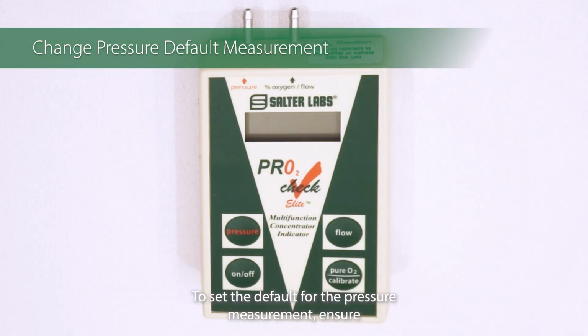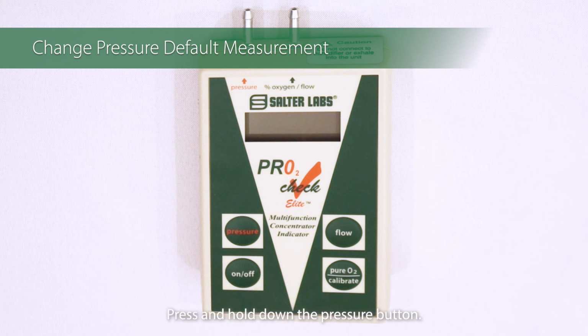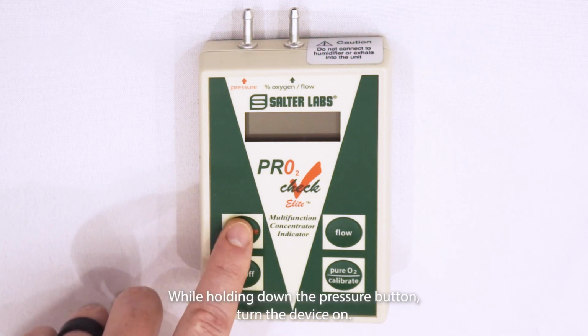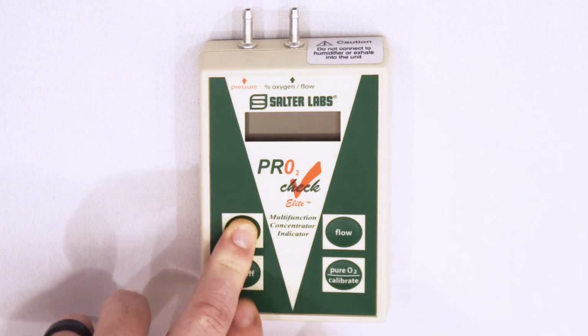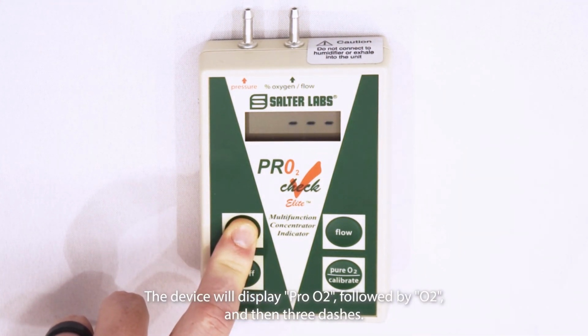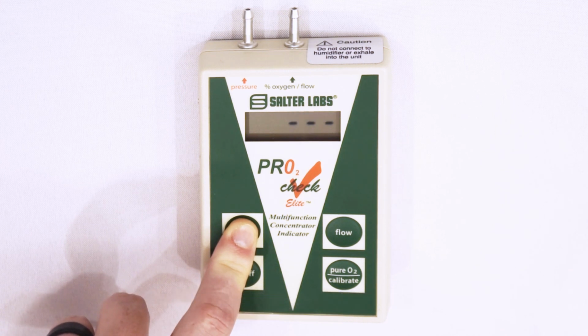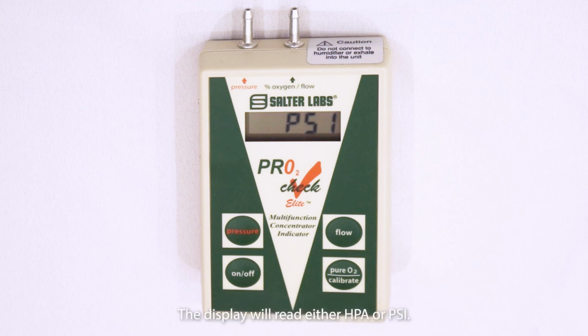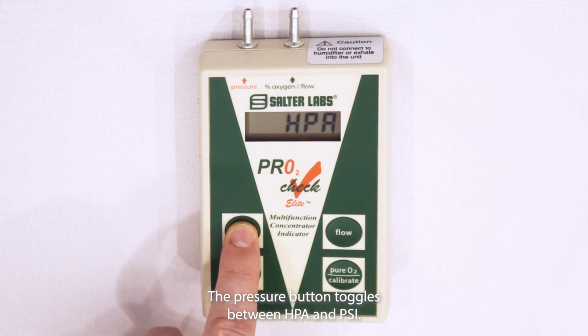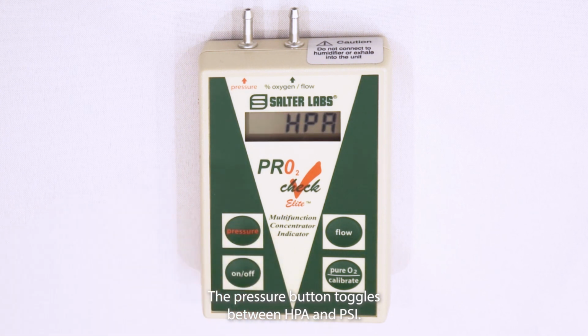To set the default for the pressure measurement, ensure the device is turned off. Press and hold down the pressure button. While holding down the pressure button, turn the device on. The device will display PRO2, followed by O2, and then 3 dashes. When the 3 dashes are displayed, release the pressure button. The display will read either HPA or PSI. Pressing the pressure button toggles between HPA and PSI. Select the desired pressure measurement and wait 10 seconds. The device returns to the concentrator mode and the default setting is automatically saved.